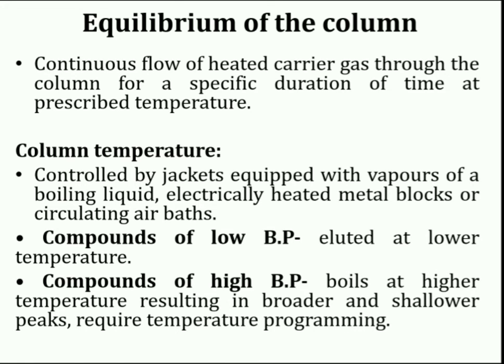Next is equilibrium of the column. The packed columns are equilibrated before introduction of the sample. This is done by allowing continuous flow of heated carrier gas through the column for a specific duration of time, usually 24 hours, at prescribed temperature.